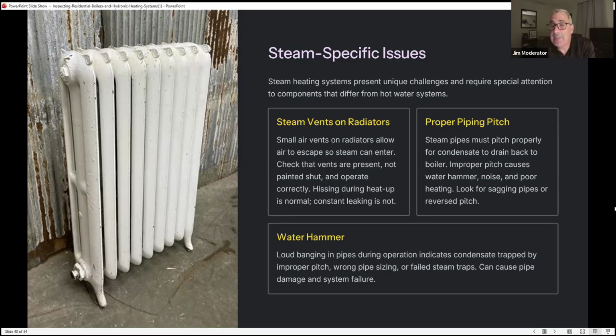We want to look for a proper pitch. Steam pipes must be pitched properly for condensate to drain back to the boiler. Improper pitches cause water hammering, noise, and poor heating. You want to look for sagging pipes or reverse pitch.